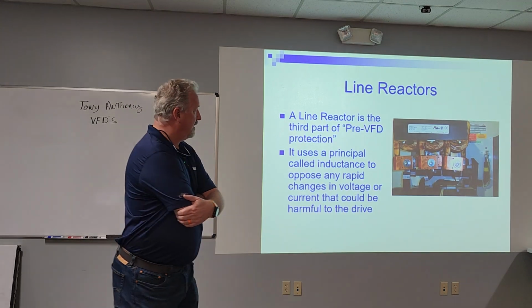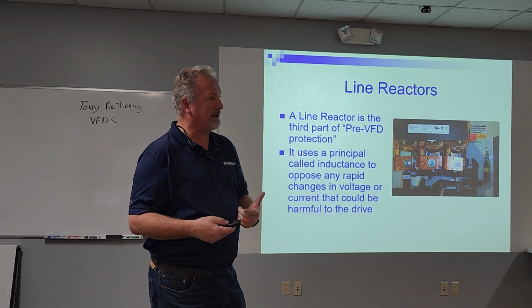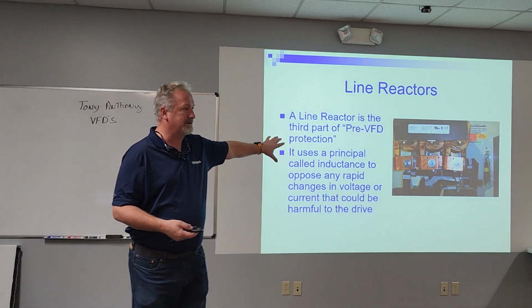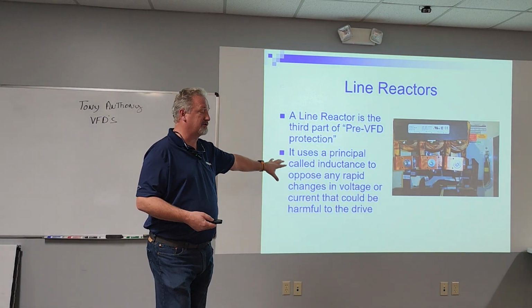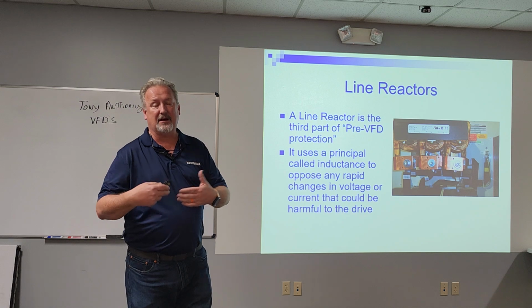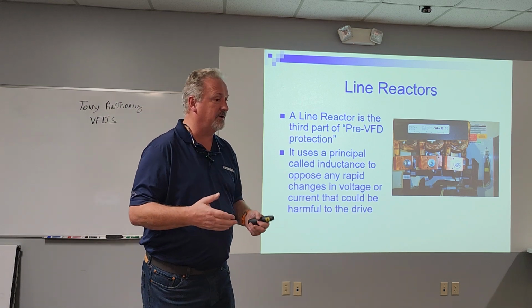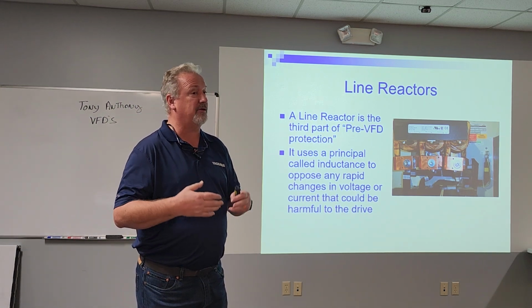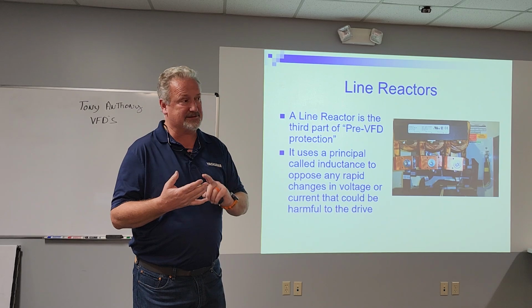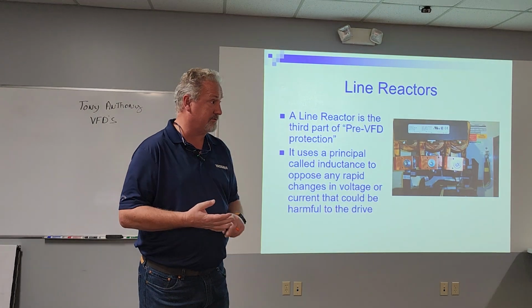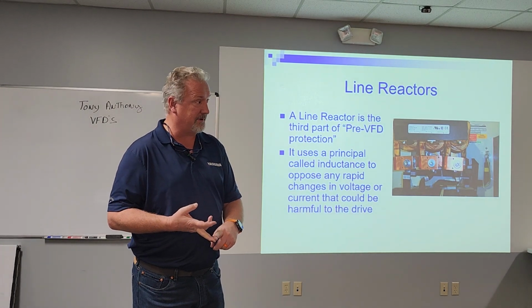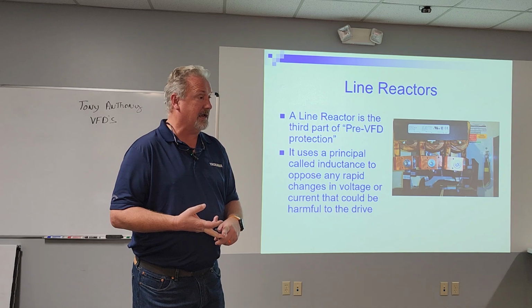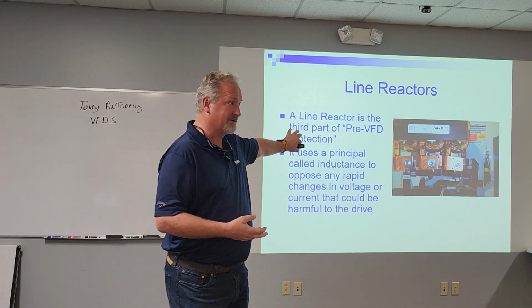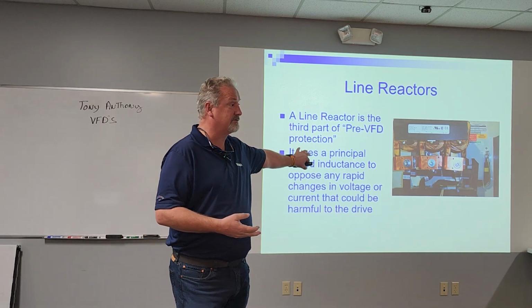Interesting. And the thing is, if you're having harmonic issues, you're probably going to be doing more than this. There's other things we can do. There's special drives we can use. And things. So if you've got a customer and they're having major issues with sensitive labs, or they are having troubles with their transformer, or breakers tripping unexpectedly, and they've just put some drives in, maybe this is something that can actually solve some issues pretty quickly.